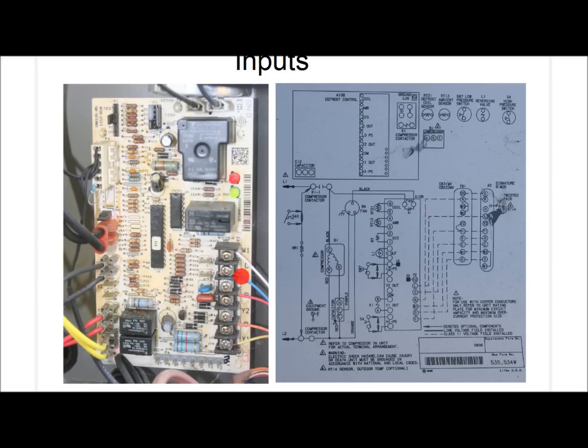Then we have the C terminal, which is the common 24 volt common terminal. Now if you don't have 24 volts on, we'll go back to the R terminal. If you don't have 24 volts on that R terminal, this entire control board is going to be dead. Nothing's going to work. All right, so that concludes the control voltage inputs that come from the thermostat.